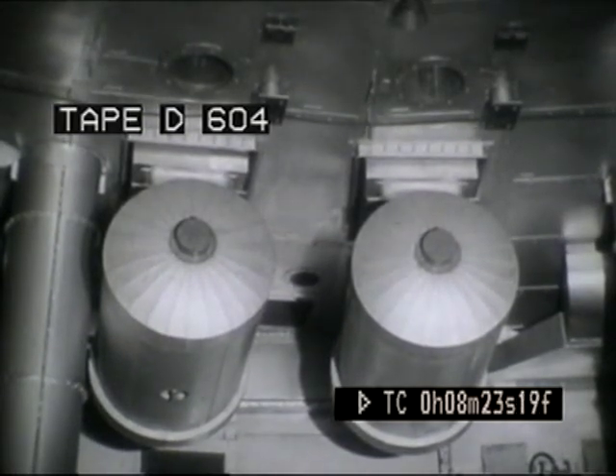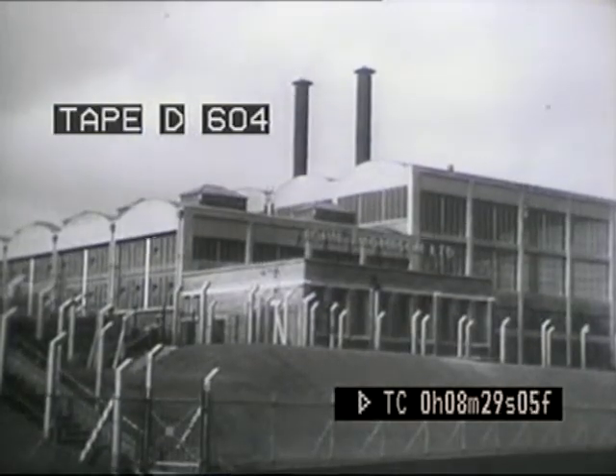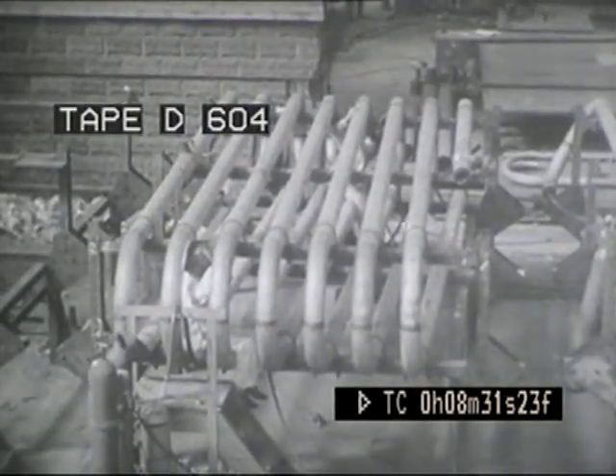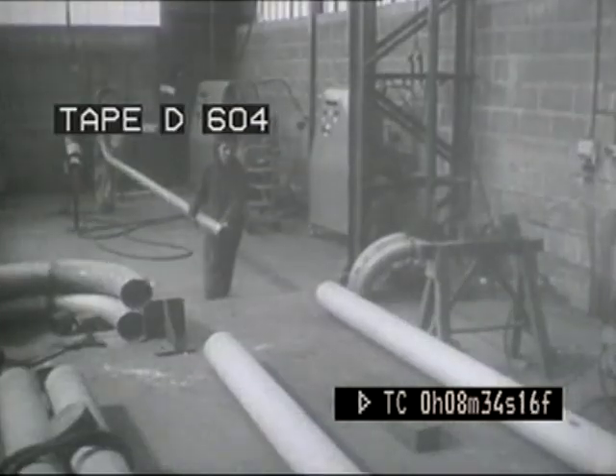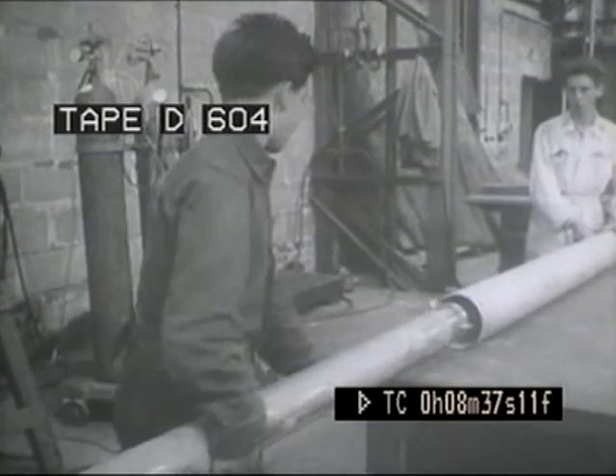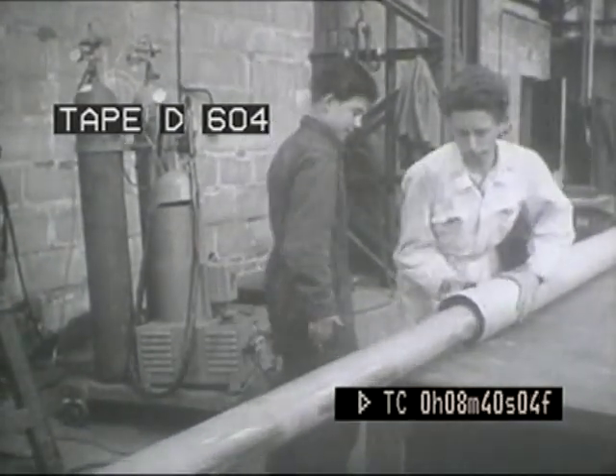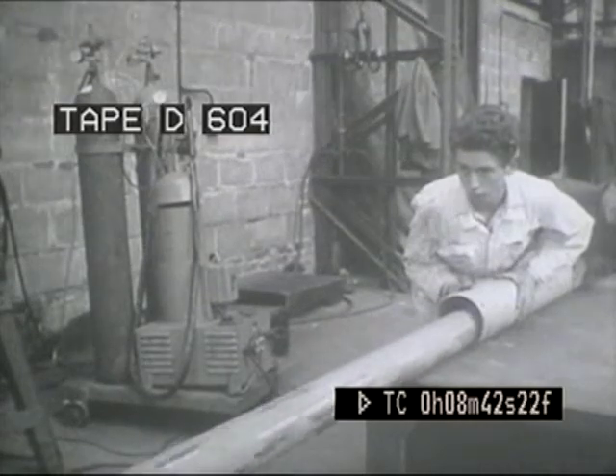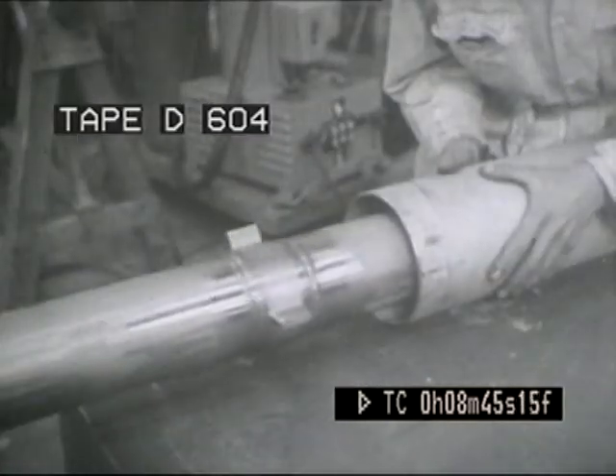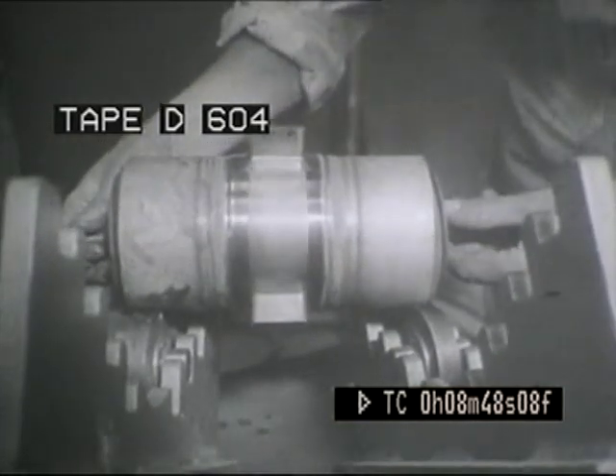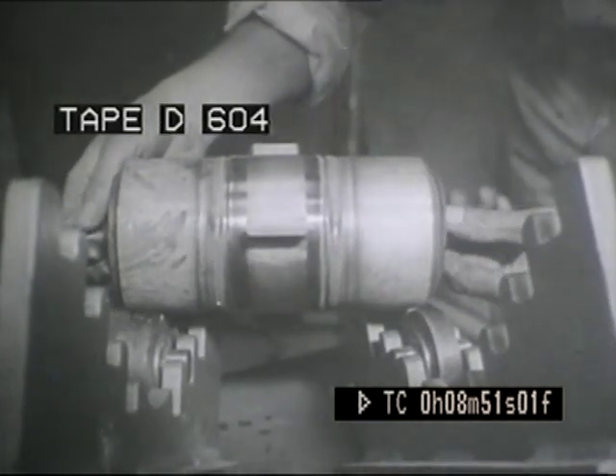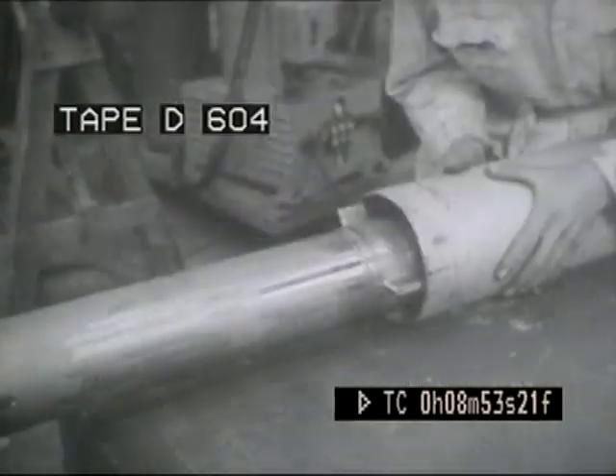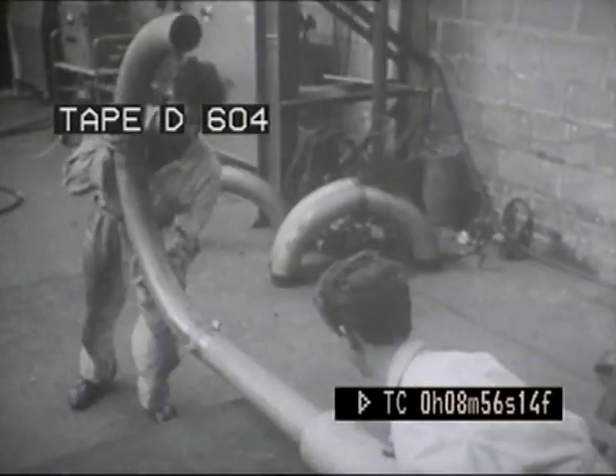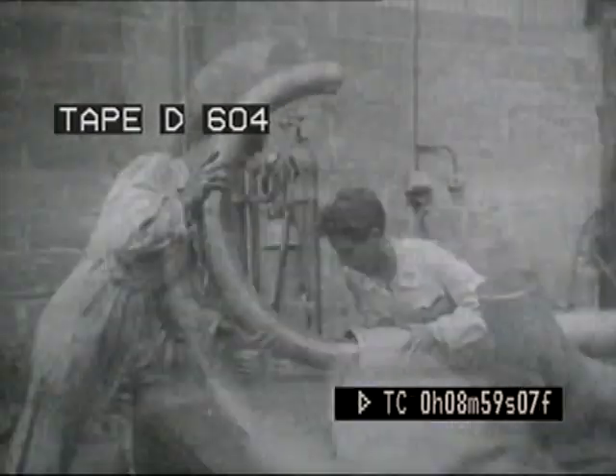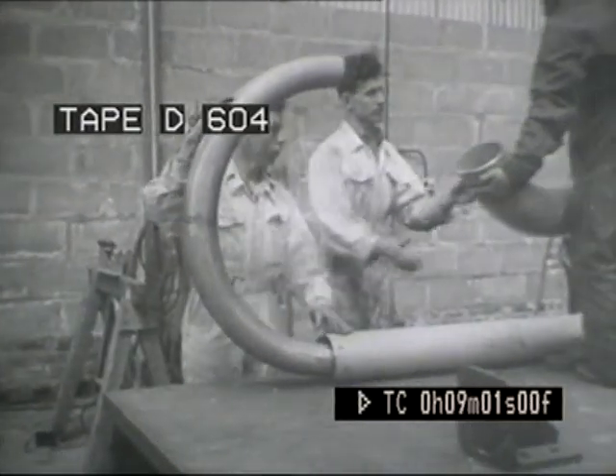After fitting the pumps, the primary heat exchangers were next to be installed. At the manufacturer's works, these units had been produced to rigid standards. They were constructed of stainless steel, continuous loops of concentric tubing forming a tube within a tube. The inner tube was held concentrically by three-legged spiders machined from solid stainless steel. Each section of inner tube was made up in the shape of a hockey stick. This was then slid into the outer tube and the return bend placed in position.